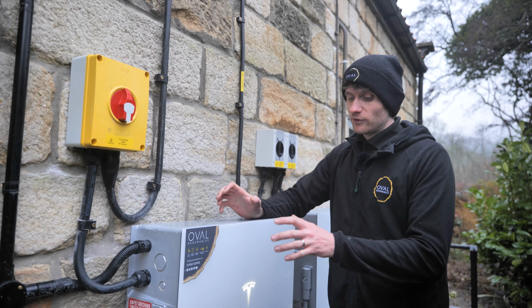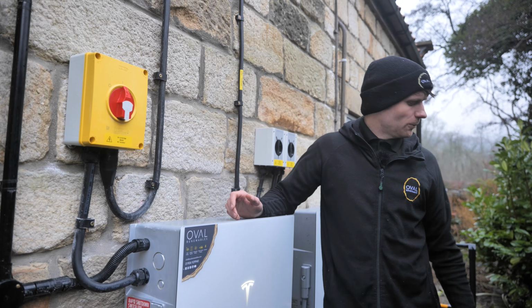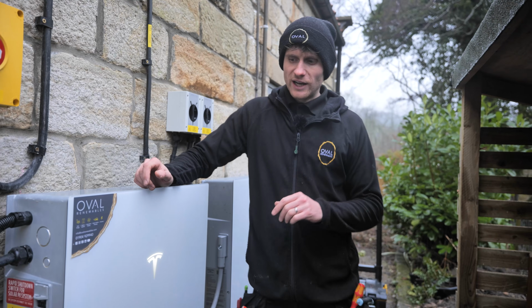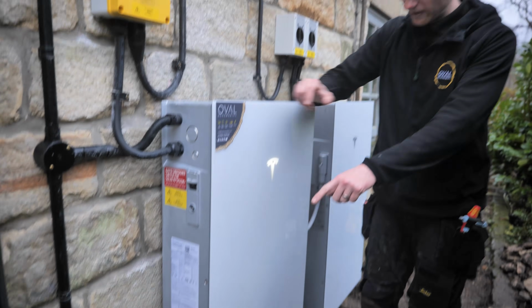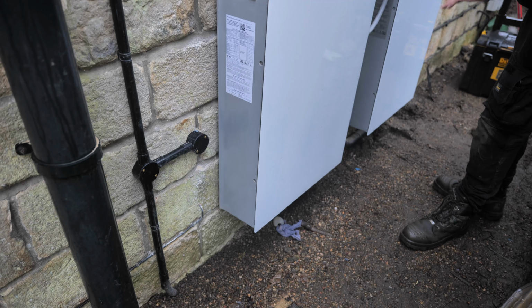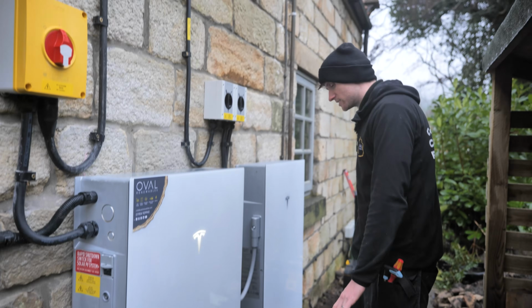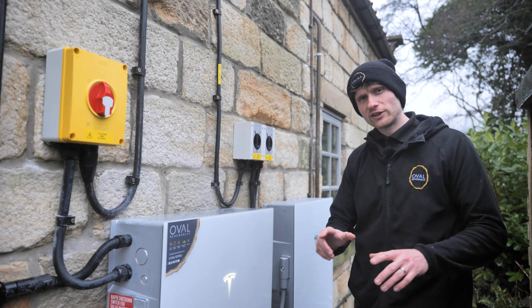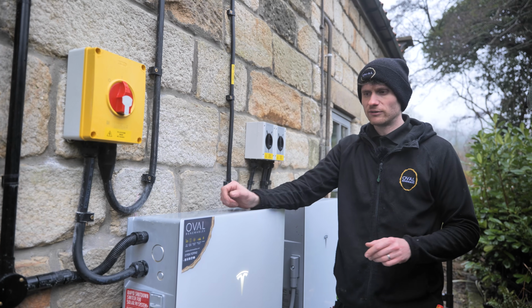So that's what we've got out here. We've also got an earth rod just behind me in a little pit, which we'll look at in a minute. That's fed underneath this gravel, which will all get put back down, and into the earth pit there. That earth cable goes all the way back to the gateway, which again we'll have a look at in a minute.